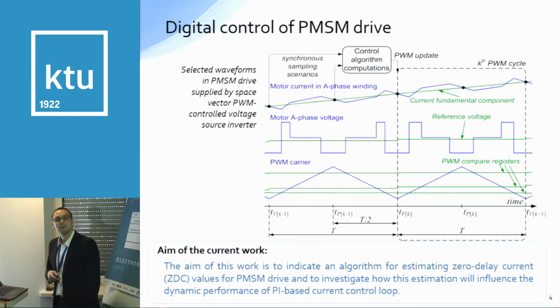And at the top there is a selected current waveform. Current waveforms, motor current waveforms, consist of a significant ripple component caused by changes in supplying voltage, and the frequency of those ripples is much higher than the control bandwidth. Therefore, control algorithms aim to control only the so-called fundamental component of these currents, the one marked in green. So the controller needs to extract this fundamental component in order to provide current controllers with proper feedback.